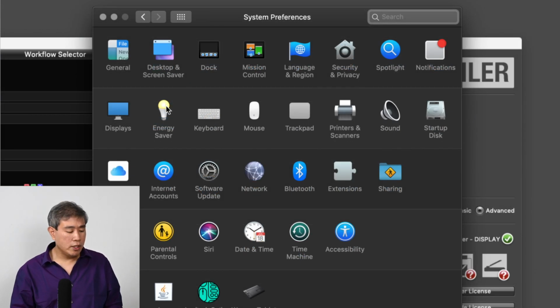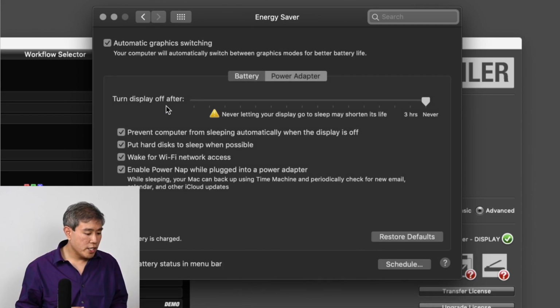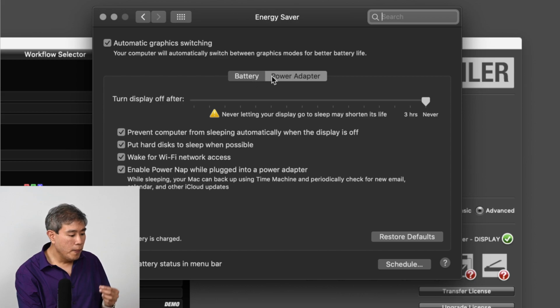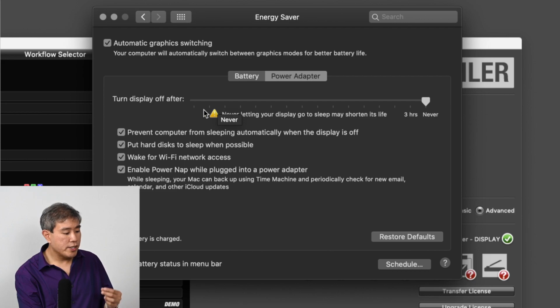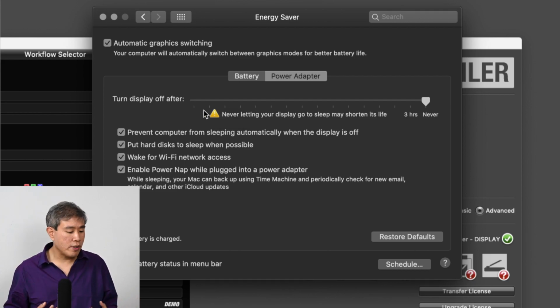The next thing we need to look at is Energy Saver, which is that LED icon right there. Under the Energy Saver settings, we want to make sure a couple of things happen. First of all, when we're on power adapter, we want to slide the slider for turn display off after however many minutes or hours to never. We're doing this so that when we do the calibration, the display won't turn off in the middle of the calibration, ruining it and forcing you to start over again. Afterwards, if you want to set it to a specific time frame that you like for the display to turn off, you can totally do that. Before the calibration, my recommendation is to set it to never. So that's the first thing.